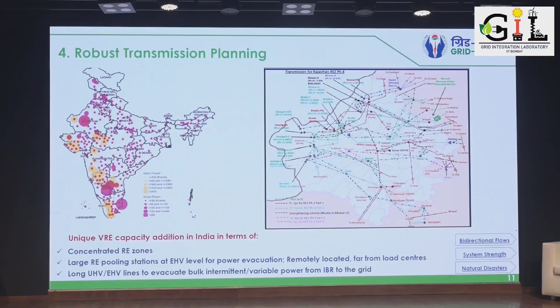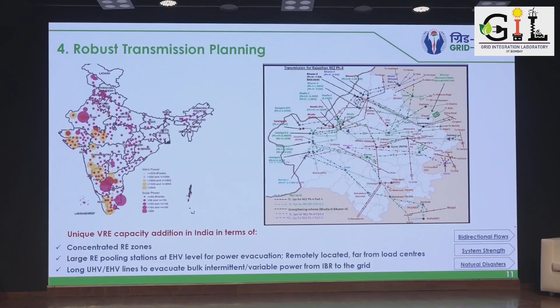These 765 kV lines generate a lot of VAR when they are loaded below their surge impedance loading. At night time there is almost no load, so we have to switch off a large number of lines, and again switch on a large number of lines during the morning hours in these areas.